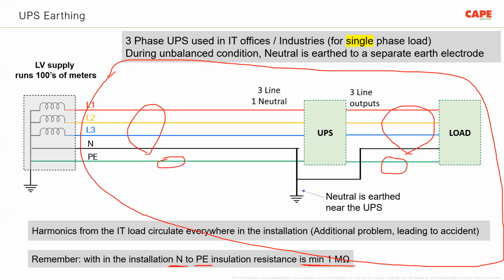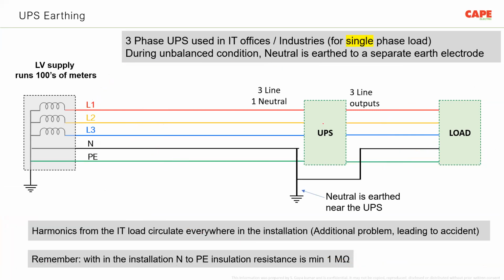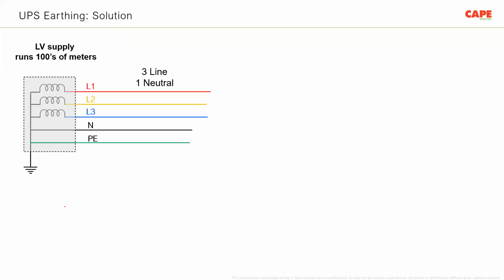The minimum insulation resistance for a healthy operation of an electrical installation, between the earth conductor and the current carrying conductors, is a minimum of 1 megohm for a 230 or 400 volt line. When the operating voltages are higher, of course, this insulation resistance also has to be higher or lower depending upon the operating voltage. So connecting a neutral to a separate earth electrode in soil, this kind of connection, is a violation of electrical safety requirement.